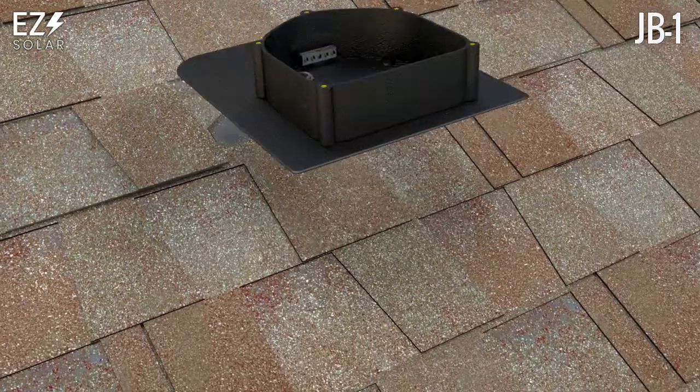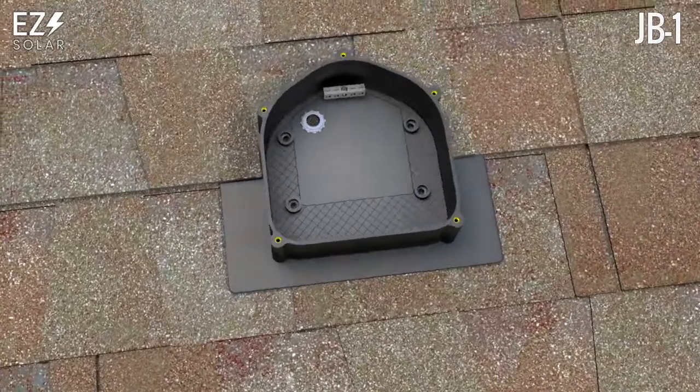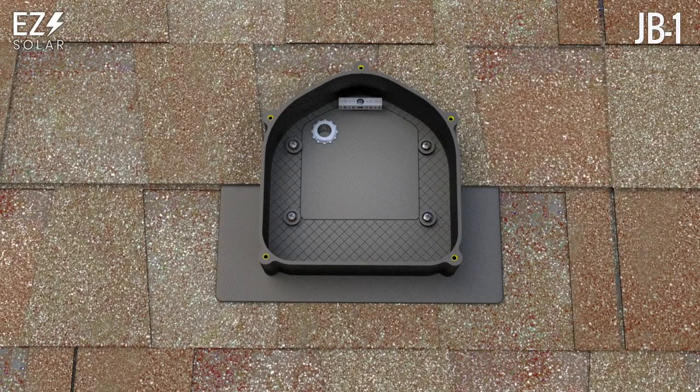Slide into place. Secure the JB-1 to the roof decking using the provided four number eight by one and a quarter screws. Torque to 15 to 20 inch-pounds or until the enclosure is snug against the shingles.